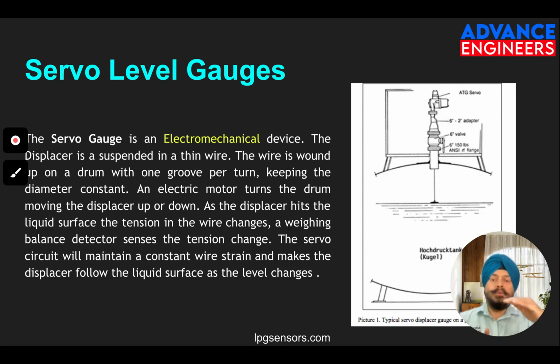As the buoyancy acts, the float starts floating on the liquid. The wire hangs from the top and tension is maintained; as soon as the float touches the liquid level, the tension automatically reduces. If you look at the top of the servo gauge, you can see this mechanism: a motor, a calibration, a valve, and a steel well, with a float in the center.